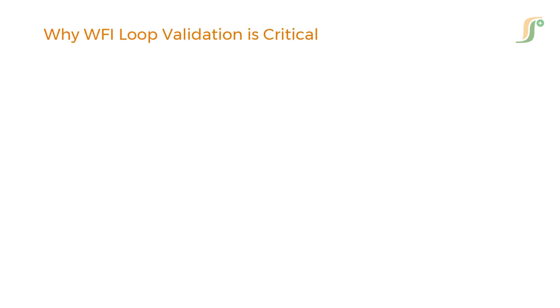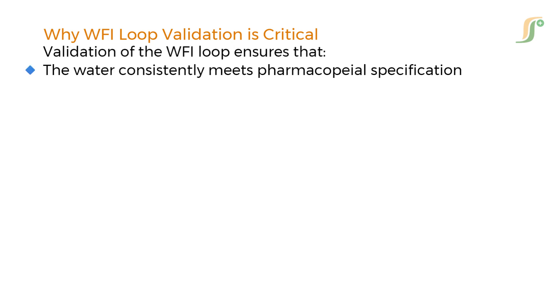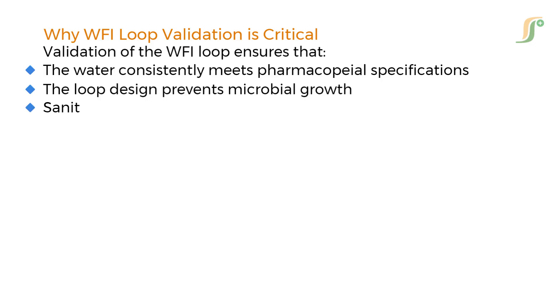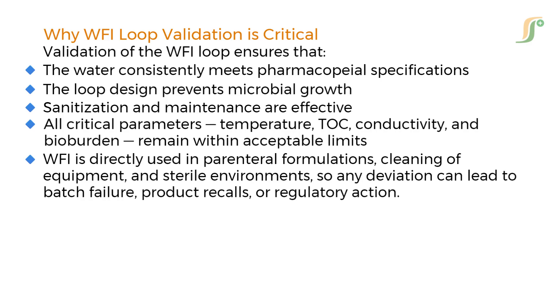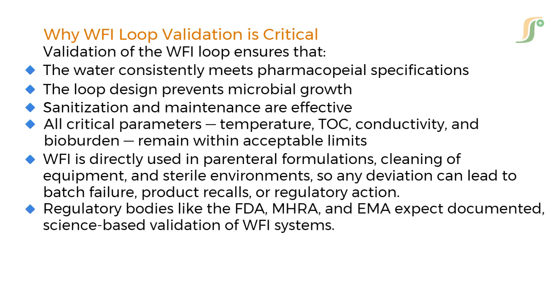Why is WFI loop validation critical? Validation of the WFI loop ensures that the water consistently meets pharmacopoeial specifications, the loop design prevents microbial growth, and sanitization and maintenance are effective. All critical parameters — temperature, TOC, conductivity, and bioburden — remain within acceptable limits. WFI is directly used in parenteral formulations, cleaning of equipment, and sterile environments, so any deviation can lead to batch failure, product recalls, or regulatory action. Regulatory bodies like the FDA, MHRA, and EMA expect documented, science-based validation of WFI systems.